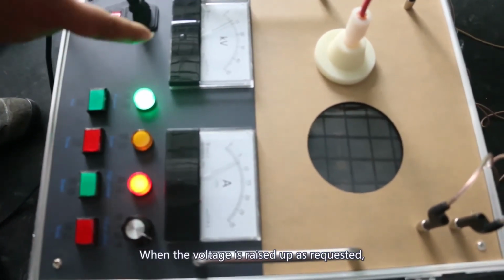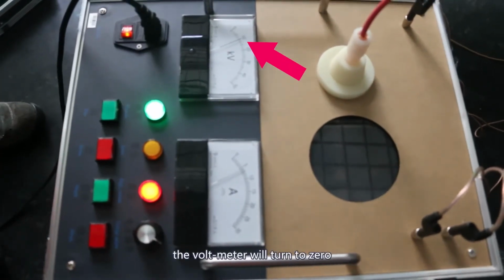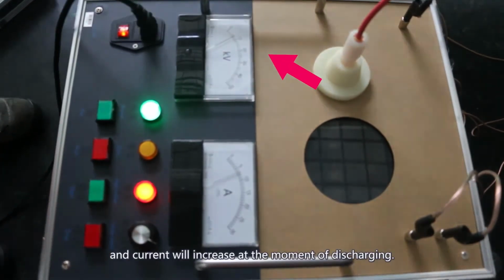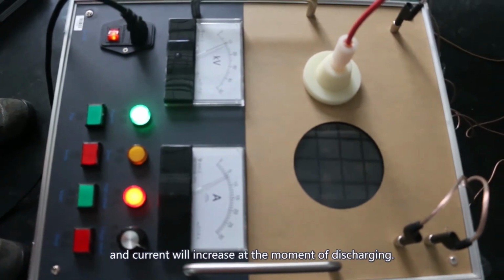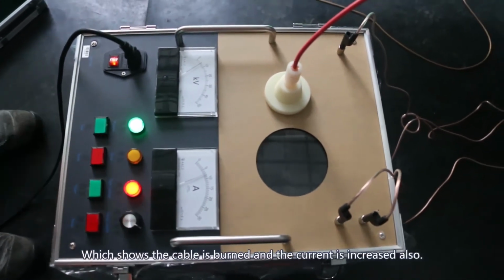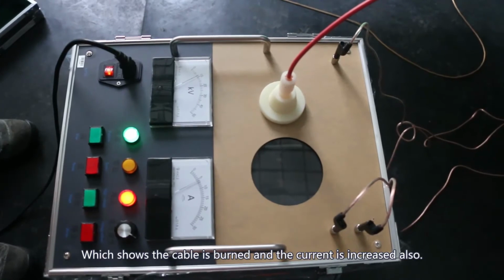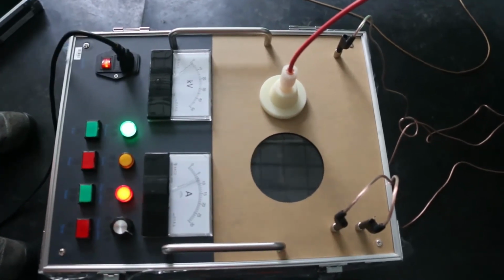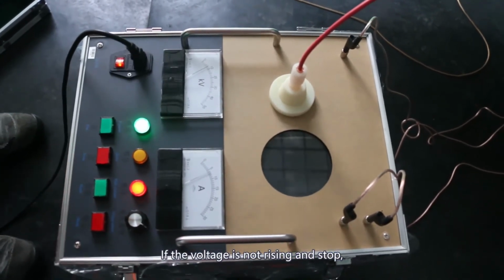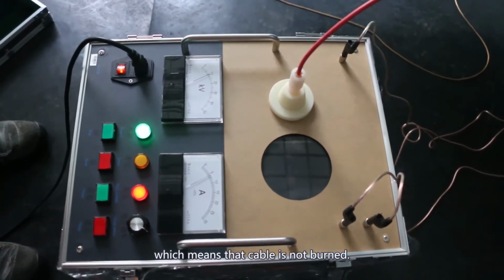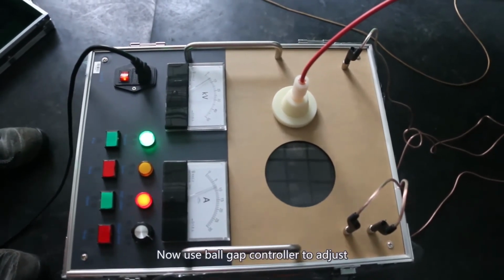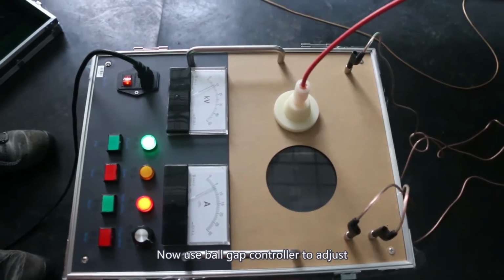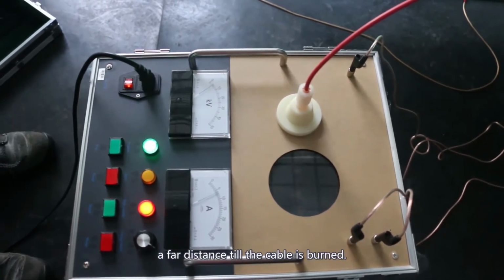When the voltage is raised up as requested, the voltmeter will turn to 0 and current will increase at the moment of discharging, which shows the cable is burned and the current is increased also. If the voltage is not rising and stops, which means that cable is not burned. Now use ball gap controller to adjust a far distance till the cable is burned.